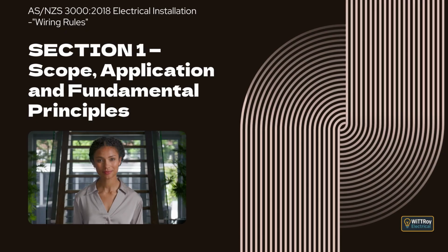Clause 1.5.8, Protection against thermal effects in normal service. This clause deals with preventing fires caused by heat from electrical equipment. Electrical installations must be arranged so that high temperatures, electric arcs, or other heating effects cannot ignite flammable materials. Equipment must be installed so its temperature characteristics, during normal use, do not create risk to people, to livestock, or to property. Heat produced in normal service must not cause damage to the equipment itself, or to adjacent materials, or to any other installation. If heat is expected, adequate ventilation must be provided to keep temperatures within safe limits. The standard reminds us that temperature can affect the performance and lifespan of electrical equipment, so installation choices must take this into account.